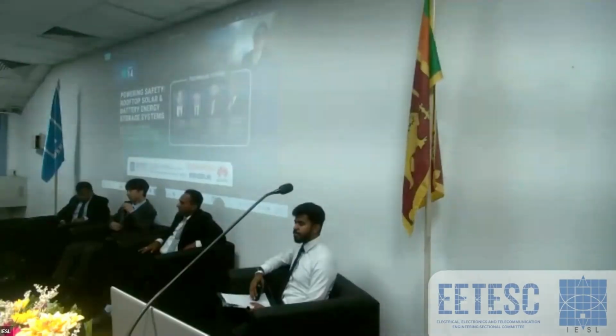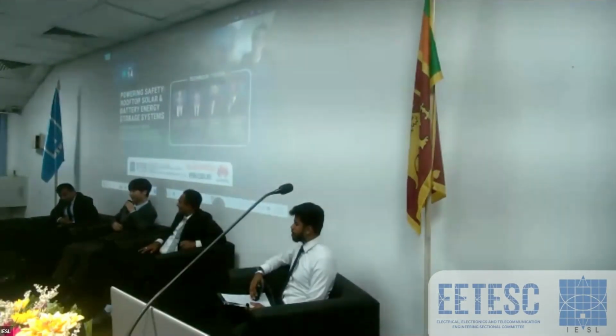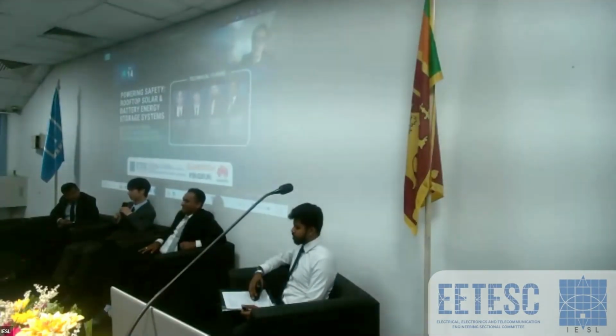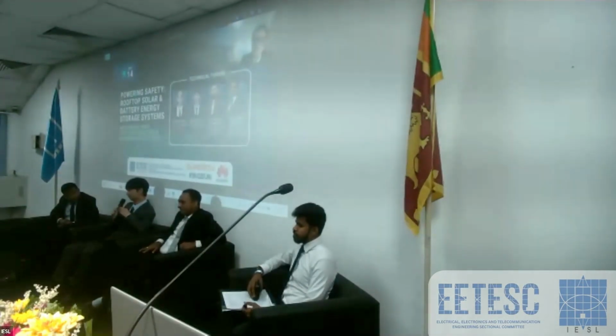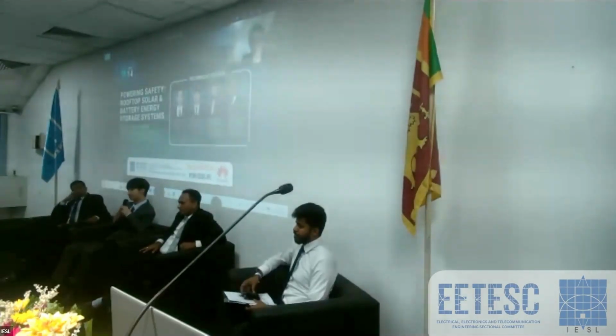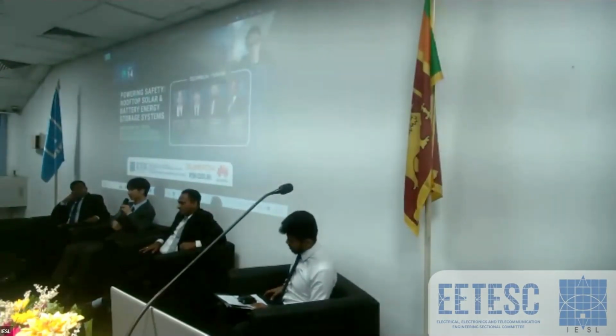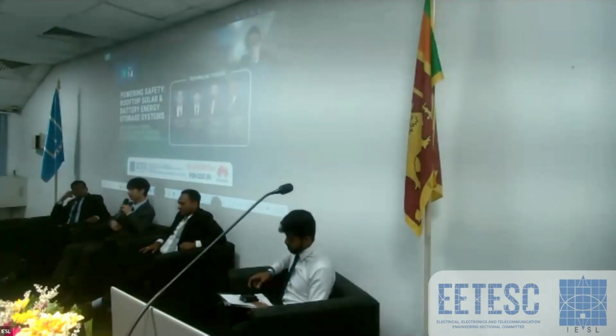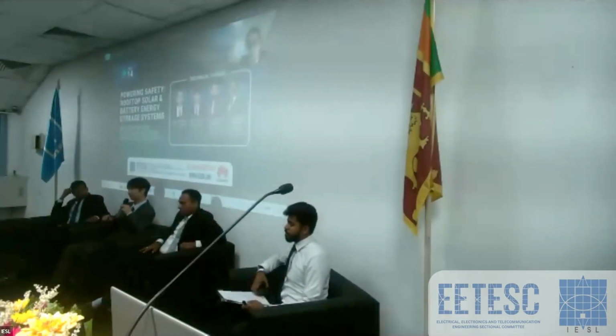For the high voltage, as I mentioned in the slides, we do have the rapid shutdown. Right now in Sri Lanka, it's an option. But in other countries like Thailand, it's necessary to equip the PV system with the rapid shutdown. So when an emergency situation occurs, like a fire, you can use the emergency button to stop the high voltage within 20 seconds. So that's how it works.